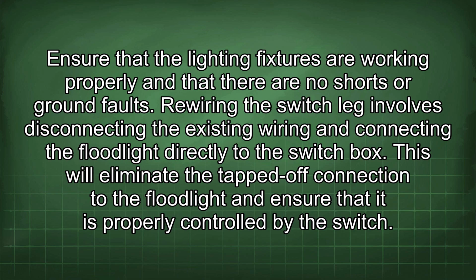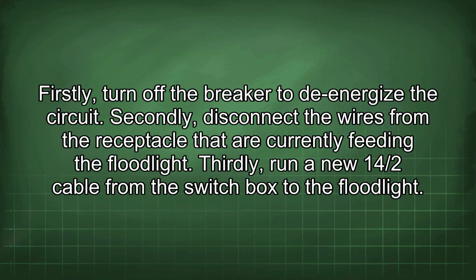Rewiring the switch leg involves disconnecting the existing wiring and connecting the floodlight directly to the switch box. This will eliminate the tapped-off connection to the floodlight and ensure that it is properly controlled by the switch. Firstly, turn off the breaker to de-energize the circuit. Secondly, disconnect the wires from the receptacle that are currently feeding the floodlight.